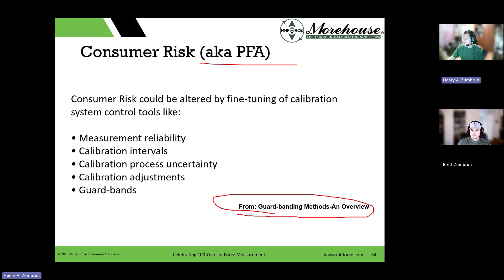The consequences of PFA, stated several times, is you're calling something bad when it's good. Your calibration provider did the unnecessary rework. They adjusted it, and now you're being told it was bad, they adjusted it, and you're told it's now good. You use it to make measurements, and it's probably really bad, which is the proverbial word salad mess. So what you need to know is you need to deal with that out of tolerance report. It might mean that I have to recall product or calibrations that were actually good.